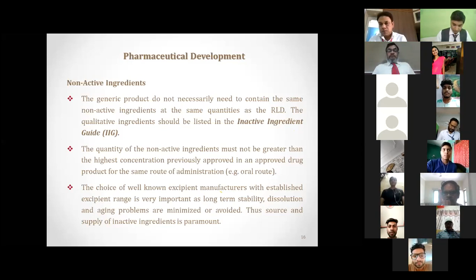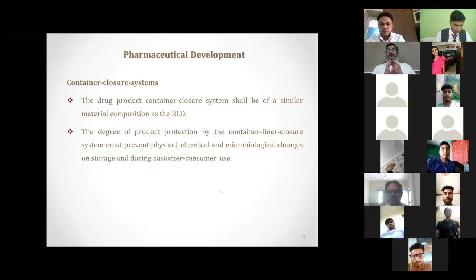As I said, the container closure system shall be similar in material of composition to the RLD. The degree of product protection by the container liner closure system must prevent physical, chemical, and microbial challenge on storage and during customer usage. So we have to target the customer, not just what we have developed and did stability for, 6 months or 1 year or so. One has to be very clear that the product has to reach the customer, and the customer is going to use it for another 24 months. He may open, close it, may not close it properly, etc. There could be hundreds of variables involved, and therefore our product, our system, our container closure has to be such that there is no impact of adverse conditions on the product.